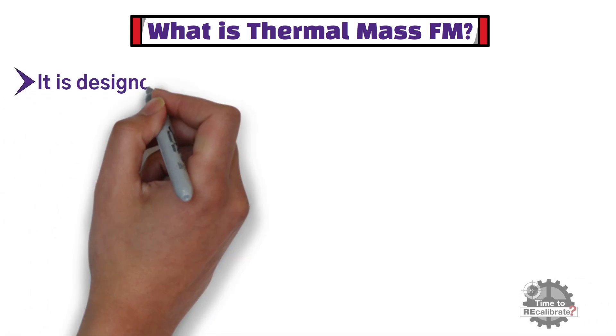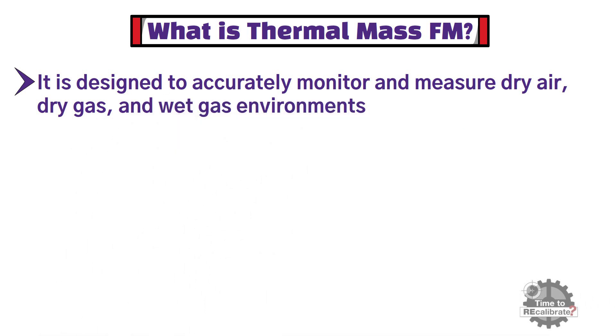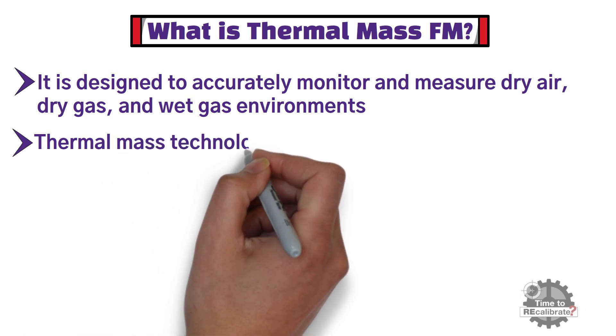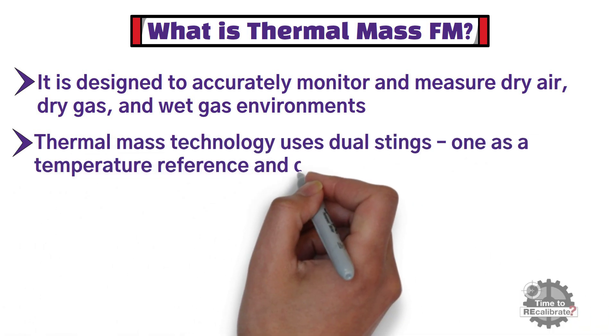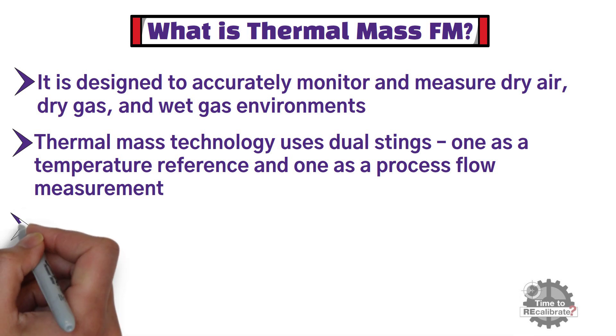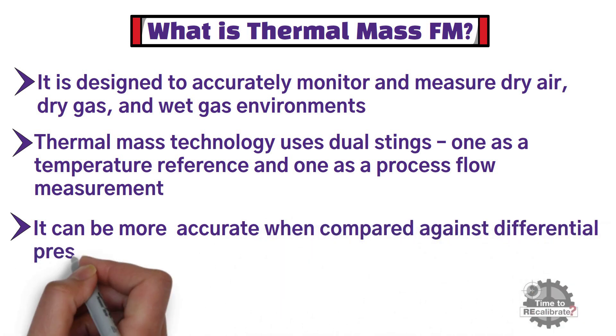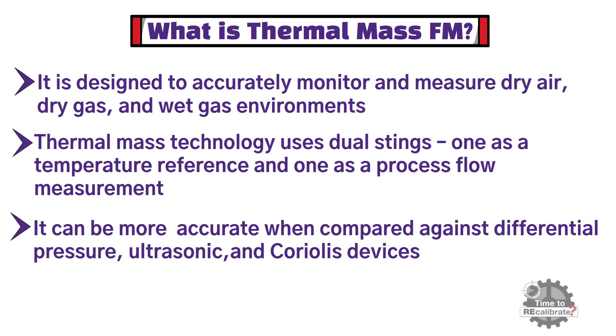Thermal mass flow meters are designed to accurately monitor and measure dry air, dry gas, and wet gas environments. Thermal mass technology uses dual stings — one as a temperature reference, and one as a process flow measurement. These devices introduce heat into the flow stream, using the concept that stronger flows cause a greater cooling effect. Thermal mass technology can be more reliably accurate when compared against differential pressure, ultrasonic, and Coriolis devices, and it can be much more cost effective in purchase, installation, or maintenance costs.